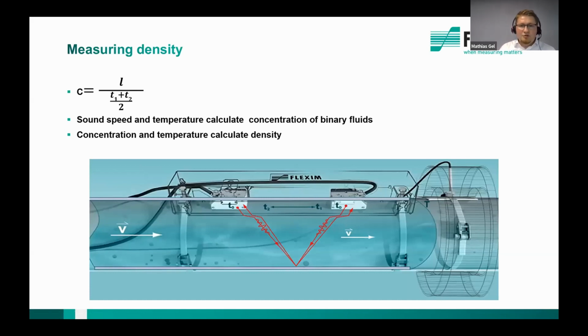What we do here is we use the sound speed measurement, right? Because sound speed is just like we would know density, refractive index, conductivity, viscosity. It's a basic property of any substance. And so the sound speed of a medium relates to its concentration, can be related to its density. How we measure the sound speed is, in theory, very simple. In practice, obviously, there's a lot of calculation software and electronic hardware involved. But the theory is quite straightforward.